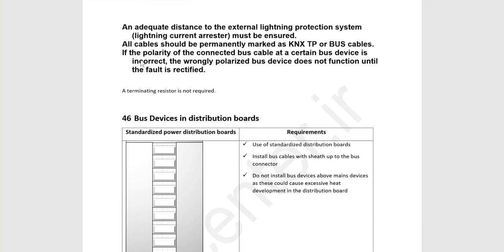Another important thing is if you change the polarity in connection, so instead of connecting red to the red connector and black to the black connector, you do it vice versa, it won't be a problem. The device just won't work, because the device has a polarity reverse check, so you can always change it the right way and it will work. The important thing is a terminating resistor is not required in KNX wiring, so we do not use a terminating resistor in KNX, but we use it in Modbus or BACnet.